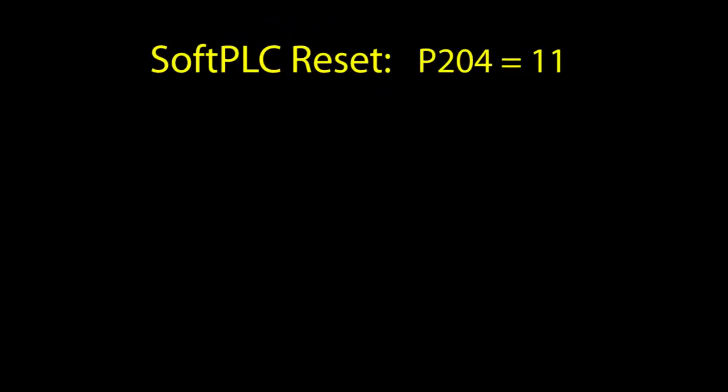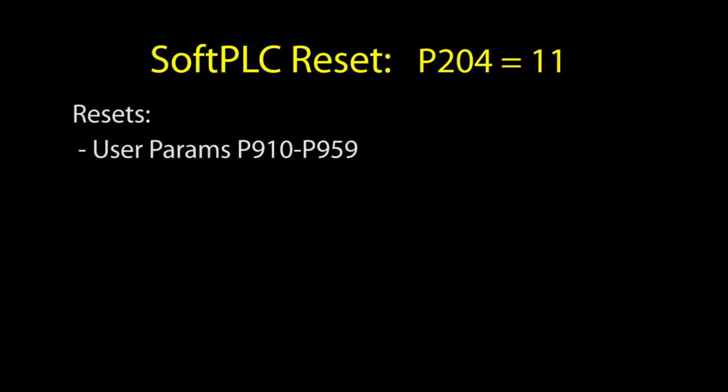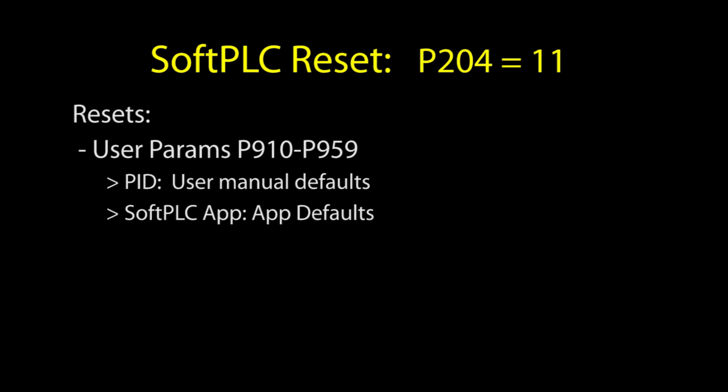You can also reset only the soft PLC parameters by setting parameter 204 to an 11. If you are running the built-in PID function, that resets parameters 910-959 to the factory defaults shown in the user manual. If you are running a custom soft PLC app, then it resets those parameters to whatever defaults the soft PLC app had set up.